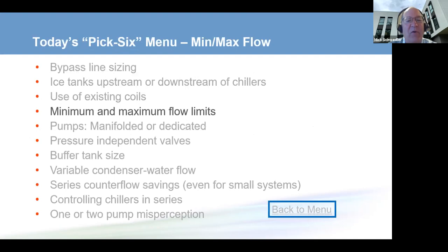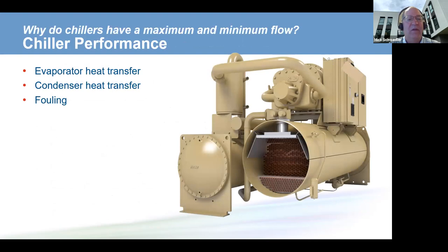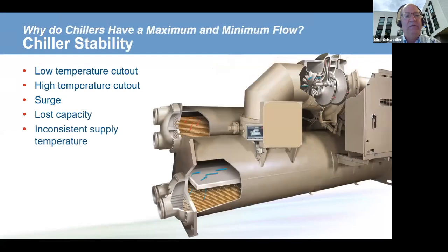Okay, next, your Board of Governors chose minimum and maximum flow limits. So all chillers have minimum and maximum flow limits. Why? Great question. We're going to find out that in a chiller, we want to have good heat transfer in the evaporator, we want to have good heat transfer in the condenser, and we want to avoid fouling in the tubes. So why do we want to have a minimum flow rate? Well, if we go below the minimum flow rate, we start to inhibit the heat transfer capability.